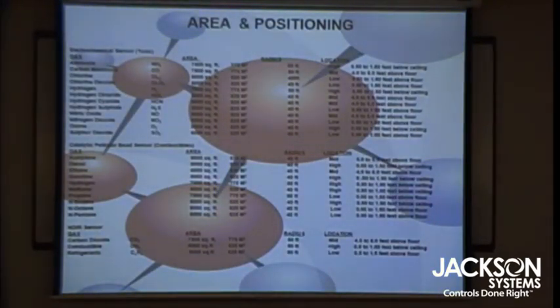So not that it's NO2, but you have all the unburned diesel components that are up there, and people get upset. So ideally, from a sales point of view, it would be nice to have the NO2 on the top and an NO2 on the bottom. And if you do have diesel vehicles or diesel pickup trucks with exhaust to the floor, you should have a sensor close to the floor. So that's just an exception to the rule, which I know you guys, we often get asked questions about that.